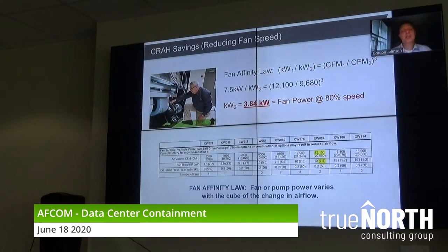That says that instead of consuming 7.5 kW of power, it's only going to consume 3.84 kW. So by reducing the fan just by 20%, you save 50% of the cost to operate that fan. That's a huge savings.